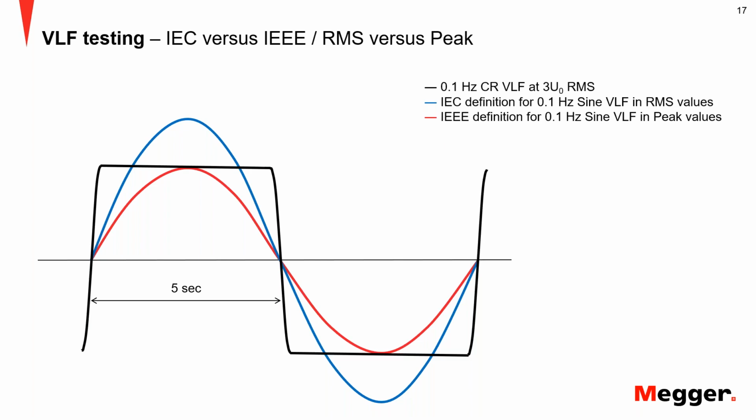So it can be argued that if you do a test according to IEEE values, you can ask the question, is that really a comparable and as good of a test as an IEC test? And unfortunately, no numbers were investigated on this. We have the 2 international studies that prove the IEC approach, and that's pretty much it. So we have to say we know this is okay, and this is probably not that okay.